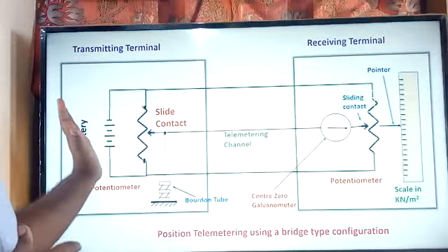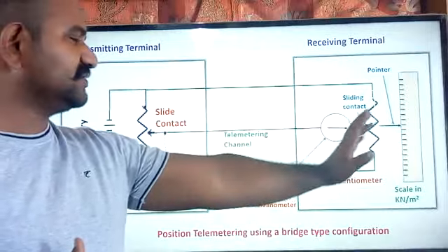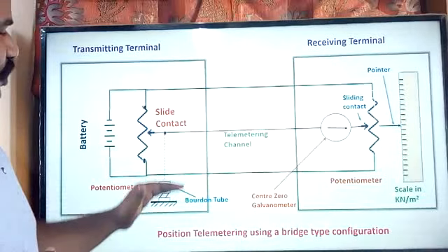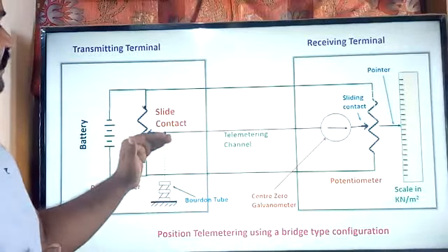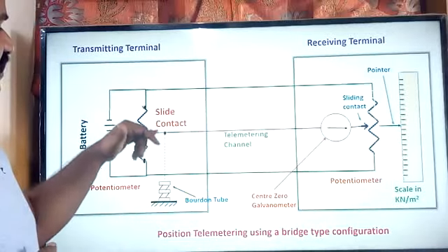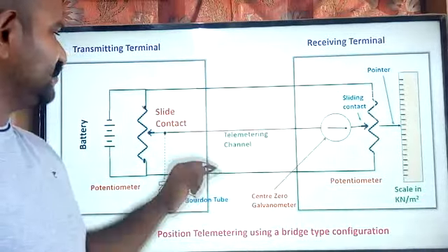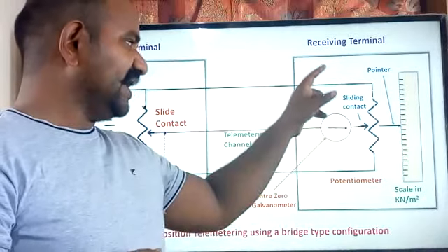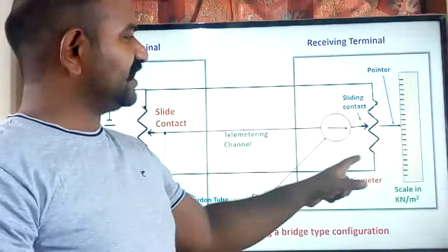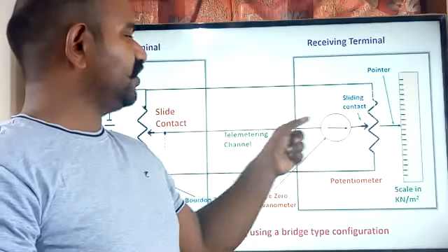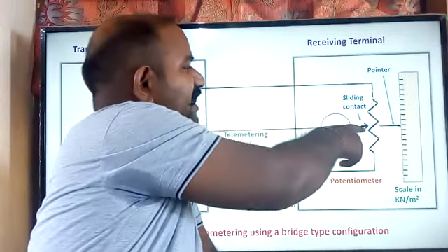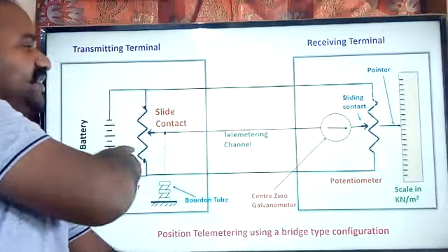Here, the same principle applies. Initially we adjust the two sliding contact positions so they are in the same position. Once we start measuring, the Bourdon tube senses information and moves the sliding contact at the transmitting end — unbalancing the bridge. That information is transferred to the receiving end, which adjusts its sliding contact to the same position acquired by the transmitting end.